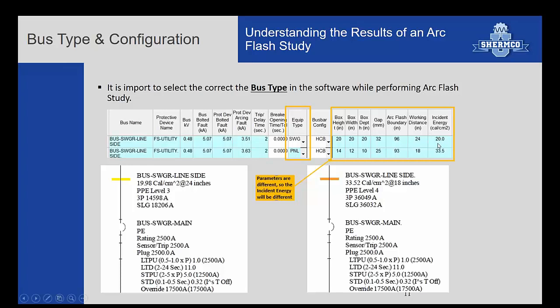20 calories per centimeter versus 33.5. So when studies are done, it's very important that the type of gear, the structure, is selected correctly. And then if you have unique things like cable termination boxes that maybe aren't standard, you might want to look at those a little more closely because it could be different.